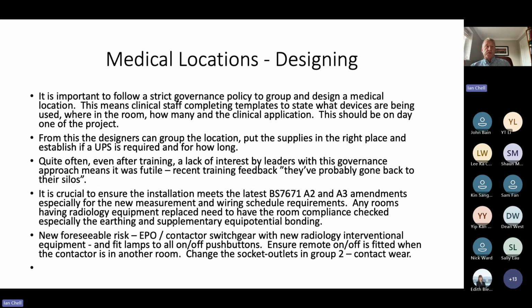Now, it's crucial, as you all know, that the installation meets the latest 7671 A2 and A3 amendments, especially for the new measurement and wiring schedule requirements. But you'd be shocked to know that in a lot of places I go to, this still isn't done. I go into a new room, I look at it, and there's no wiring schedule. Okay, I can't quote figures on how many fail, but it's still commonplace. And any rooms such as radiology need to have the room compliance checked, especially earthing and the supplementary equipotential bonding, to make sure it complies with Amendment 2 and Amendment 3.